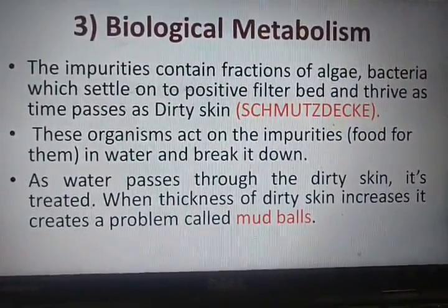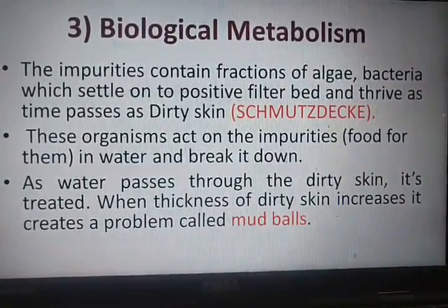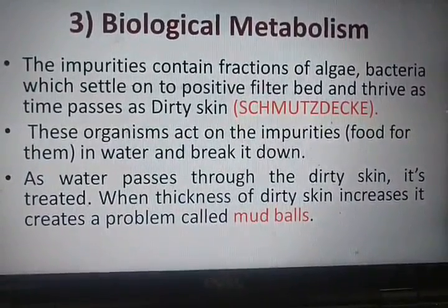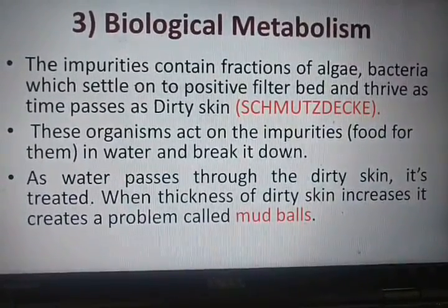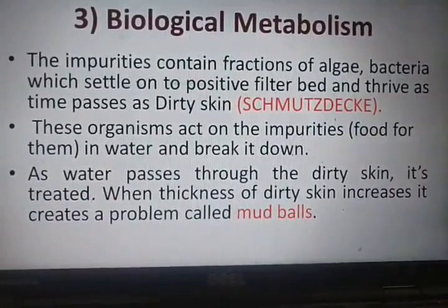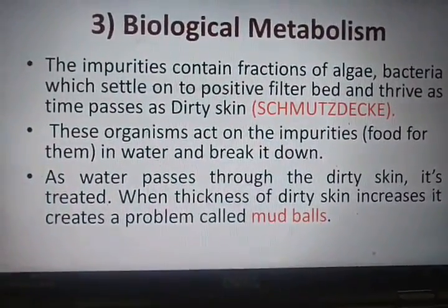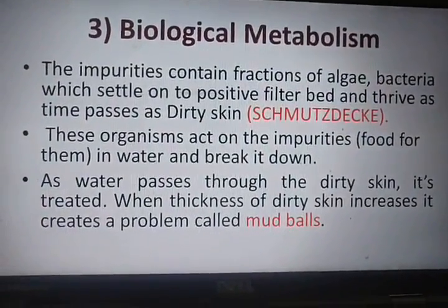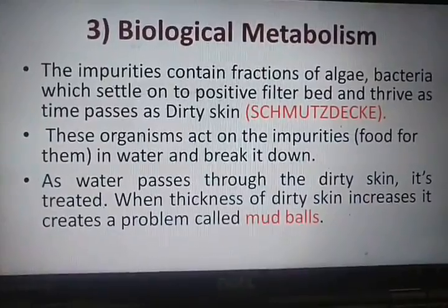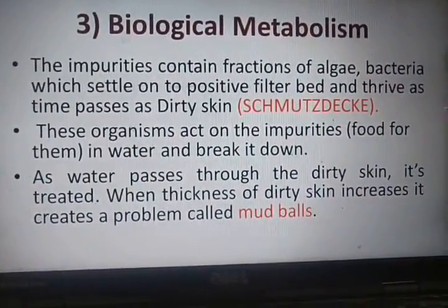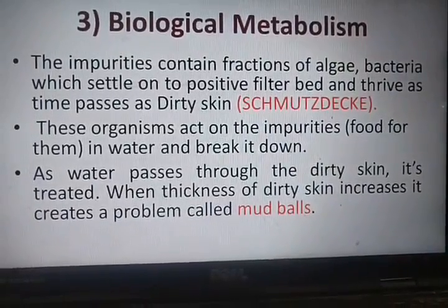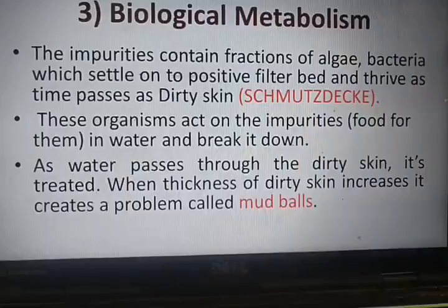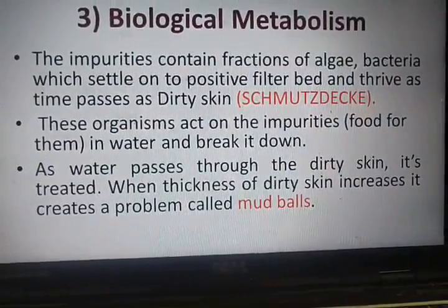When the thickness of the dirty skin increases, it creates a problem called mud balls. That means this dirty skin layer has to be removed by frequent backwashing of the filter. Otherwise, if the layer grows, it will create problems in the filter, called the formation of mud balls. We will see that in detail when we discuss problems in the filters. So this third mechanism is called biological metabolism. That is the formation of the dirty skin layer on the layer of the soil, which acts on the organic impurities specifically, breaks them down and treats the water.